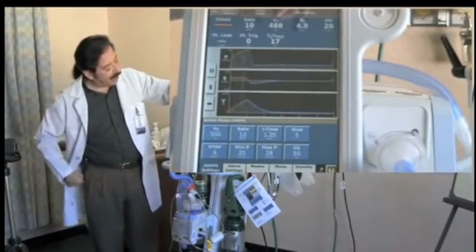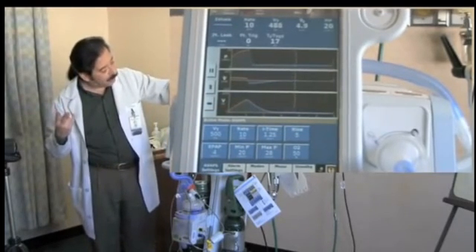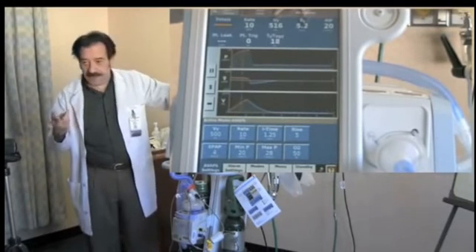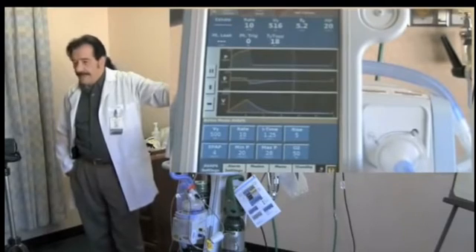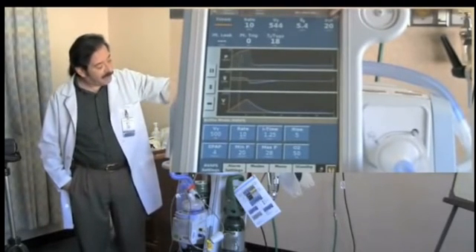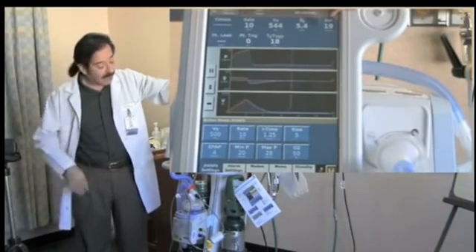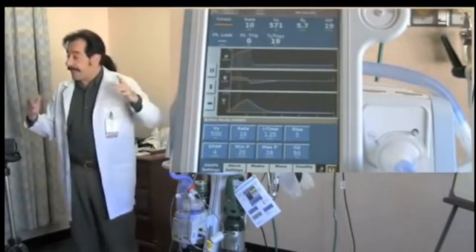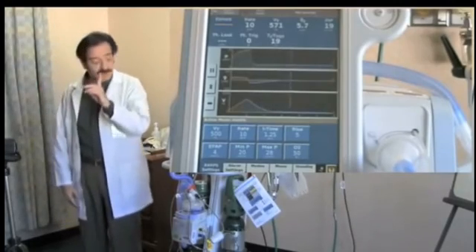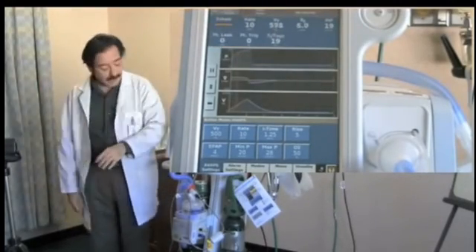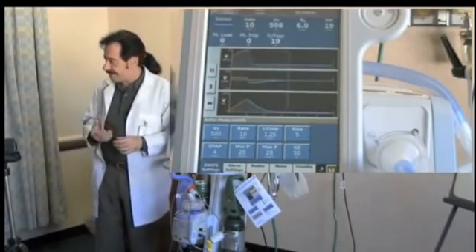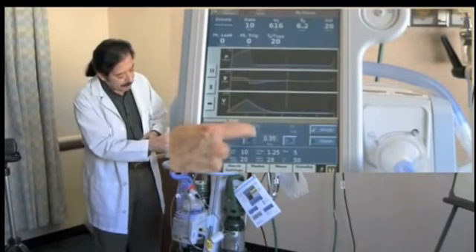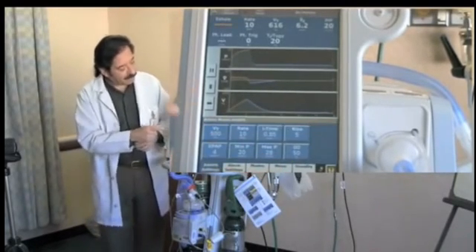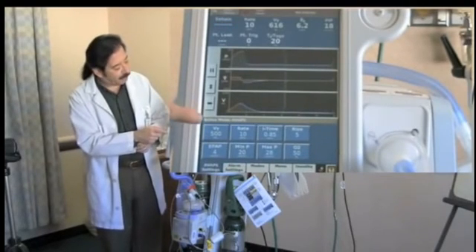So now I made those 2 settings, the P-min and the I time, and now within 3 breaths, okay, at 3 breaths, I actually hit my volume, and I overshot it. So now we're going to start seeing the peak pressure drop until it drops back down to the 500. But it's going to take a while, okay, because it only makes a change of 1 centimeter water pressure per minute, okay? So if now I'm saying, oh gosh, now I'm at 600, that's too much. Well, first I can decrease my I time, okay, and see what kind of change that has on the pressure, on the volume.